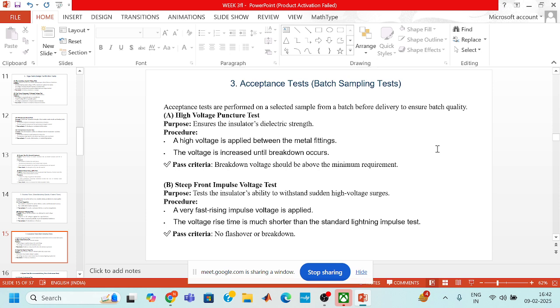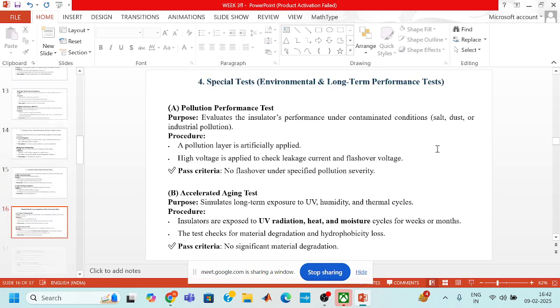This test is used for checking the ability of insulators to withstand sudden high voltage surges. The main procedure is to give a fast rising impulse voltage. There should also be a criterion that the voltage rise time is much shorter than in the standard lightning impulse test. If there is no flashover or breakdown during this, then the insulator will pass the steep front impulse voltage test.